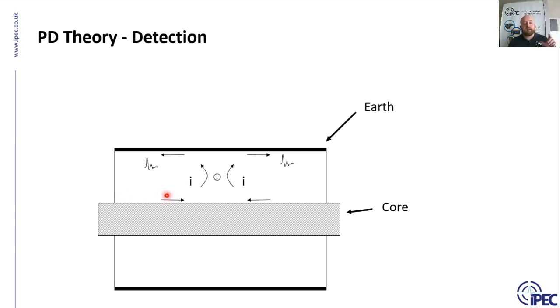So what that means is those two signals, because from the PD source it's emanated away, it's then been induced onto the inside of the earth and the outside of the core. Those two signals are equal and opposite. So if you put a sensor around the cable, you won't detect anything. So that's why we can't apply HFCTs around a cable, because we've got those equal and opposite signals inside. Those signals are traveling along the surface. They're high frequency signals, trapped inside the cable because the cable acts as a Faraday cage, so the signal cannot escape.